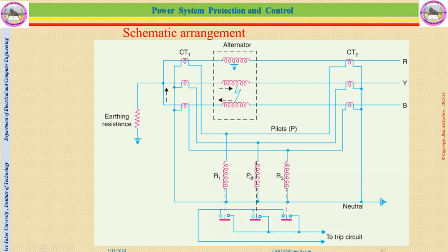So these are the relays, relay 1, relay 2, and relay 3. Those relays are related to the phases. For example, relay 1 is for phase R, relay 2 is for phase Y, and relay 3 is for phase B. There is also a tripping coil, or relay coil, connected in some conditions, and all three are connected together, and they will give a signal to the circuit breakers.